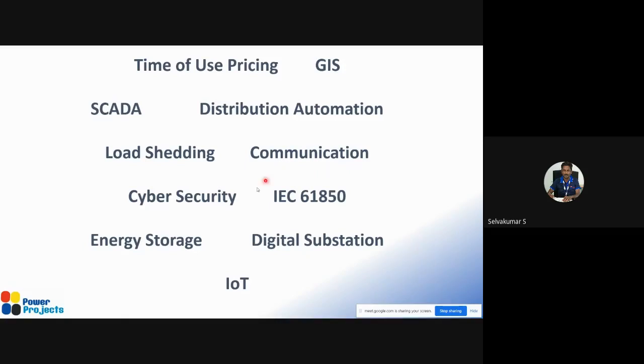Before IEC 61850 came into the picture, an ABB relay talks in some language, a GE relay talks in some language, a Siemens relay talks in some language. That means an ABB relay will not talk to a GE relay, and a GE relay will not talk to a Siemens relay. So, okay, fine. If they are not talking, what is the problem? Today I have installed a substation with an ABB relay. And tomorrow, because of an increase in demand or because of an additional transmission line, I want to extend one more transmission line bay.